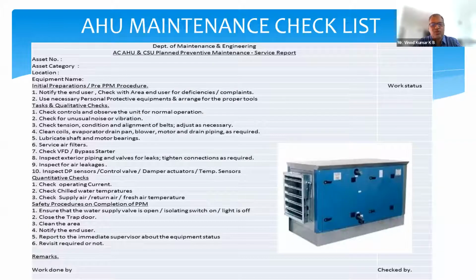The electrical parts have to be checked. You have to check both the filters in the AHUs, check for any leakages, and see if there is water dripping, whether the drain pan is clean, and whether the water in the pan is flowing through the drain and going out of the building, so that there is no water stagnation. Water stagnation is also a problem, because it will create contamination. The water dripping from the coil onto the drain pan has to go quickly into the main drain line and out of the building. So check whether the drain pan is correctly sloped and whether the water in the pan is being drained out. This checklist is mandatory. Every maintenance check has to have this checklist properly used by the team.